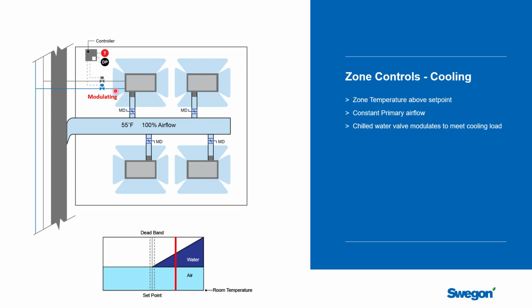So in this case, you can see how the system is going to respond. A typical flow rate for a chilled beam is about 1 GPM. So this is 4 GPM, and it's realistic that you could get a modulating valve that would have some level of rangeability, and so you'll be able to modulate that flow to meet the load. And if you look down here and you're going to provide 55 degree air, you should notice that the air can actually do some cooling effect in here.